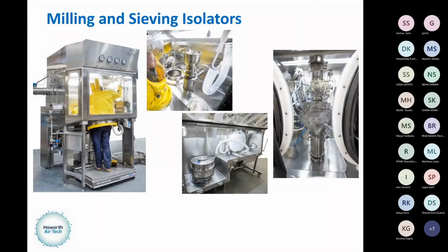And then we look at different ergonomic challenges. So in this particular example, we're using half suit technology. It's not a common technology. We do supply maybe 1 or 2 isolators a year with half suits. There are pros and cons of these systems versus glove ports.